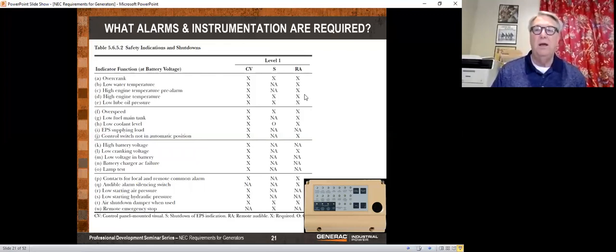And you can see for level 1, I have to have a remote annunciator somewhere, like in a hospital, it might be a nurse's station, or in a water treatment plant, or a data center, it might be where the guy sits that is looking at the screens that control the plant. And it'll basically just have an annoying piezoelectric buzzer here, and he can look at it. And so this light might come on and it'll say high battery voltage. Well, he may not know what to do about that, but he can always call somebody and say, hey, this thing is making a racket, and it says high battery voltage. What should I do about this? And then someone who is a maintenance person can come out and take care of that. Now there is a silence on here. You can push the silence and it'll turn off the annoying buzzer, but keep the light on until the alarm actually goes away.